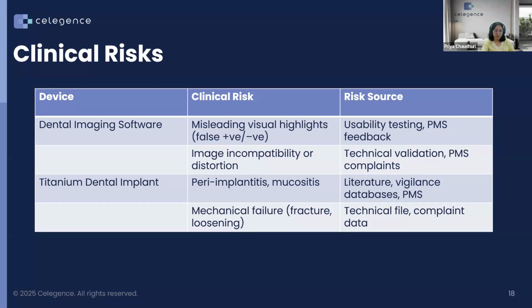So this could be documented and compared with software performance data, the PMS findings, and the PMCF findings. We typically recommend, as service providers, adding a quantifiable value, let's say a percentage of occurrence or a ratio, if it is applicable to the application in question, in the CER risk table, even if the number is an estimate from the literature. It gives the notified bodies a quantitative risk baseline and allows them to evaluate whether the benefit-risk profile is acceptable compared to published best practices and current expectations.